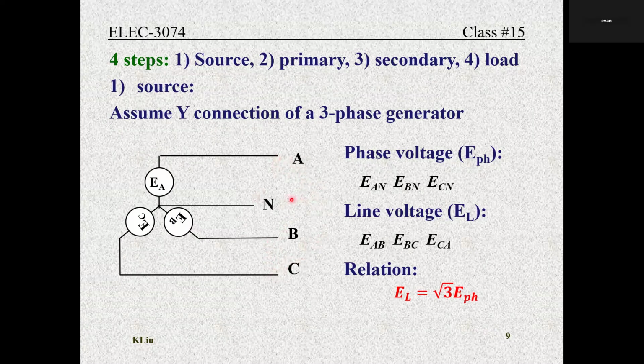Again, if the system is balanced—meaning all components are equal and connected properly—those voltages are also equal to each other, with a phase shift, though the magnitudes are the same. The relationship is: line voltage equals square root 3 times the phase voltage. That voltage is always going to be greater than the phase voltage.